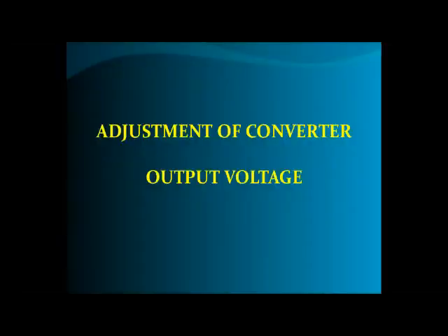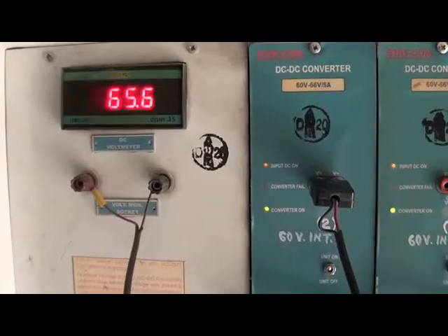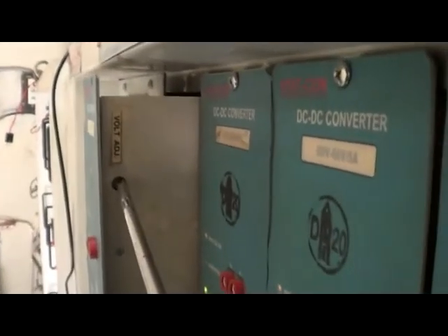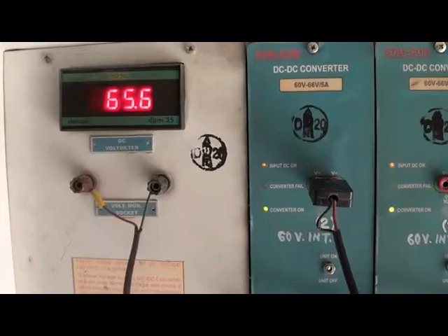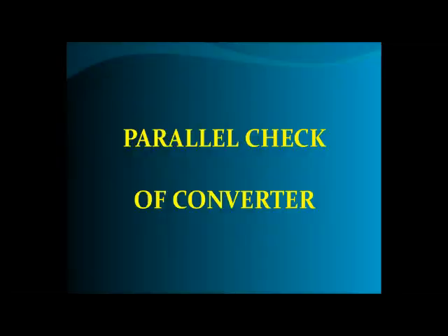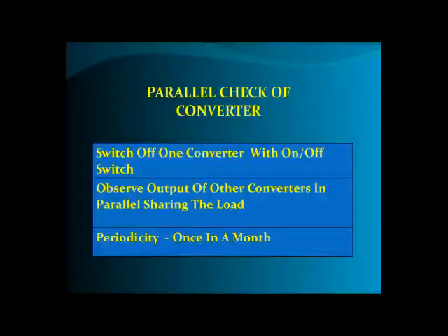Adjustment of converter output voltage: Pull the DC-DC converter out from the front. Connect test points to the common digital voltmeter. Adjust the potentiometer to get the desired output. For parallel check of converters: switch off one converter using the on/off switch and observe the output of other converters in parallel sharing the load. Periodicity: once in a month.